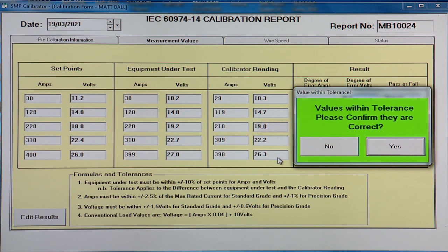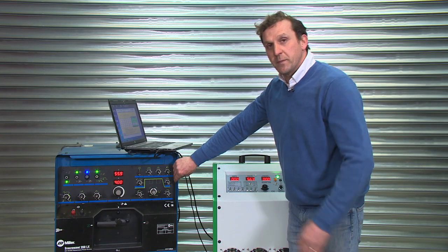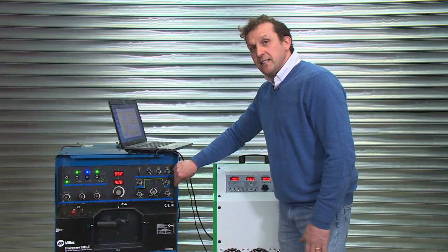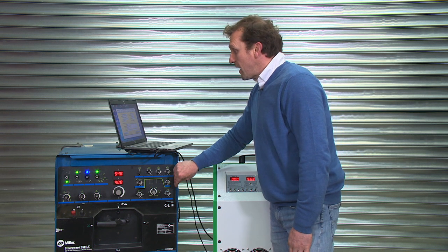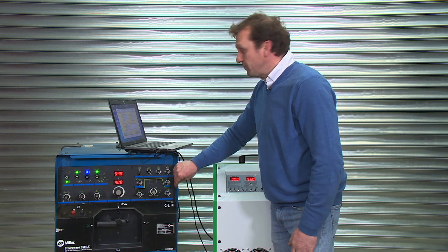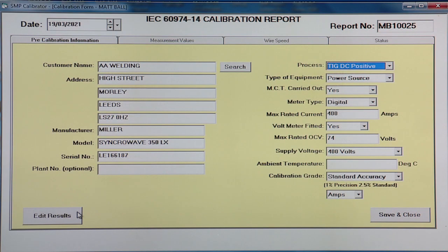Once all the results are entered, we're asked again to confirm everything's correct, yes. We're also asked, do we want to take wire speed? We've got a TIG welder, no wire speed involved, so that's a no. Because this is an AC-DC machine and the customer uses it for aluminium welding, we are going to have to calibrate in the opposite polarity. Quite simple though, on the program, just hit the button, calibrate in opposite polarity.